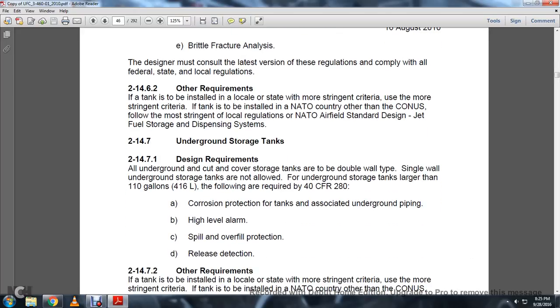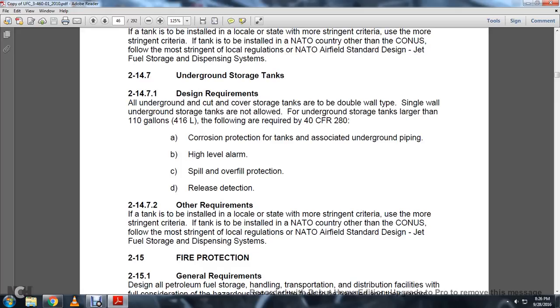214.7 The underground storage tanks. 214.7.1 Design requirements: all underground cut and covered storage tanks shall be the double wall type. The single wall underground storage tanks are not allowed for underground storage tanks larger than 110 gallons. The following are required in Title 40 CFR Part 280: the corrosion protection of the tanks and associated underground piping, high level alarm, spill and overfill protection, release and detection.